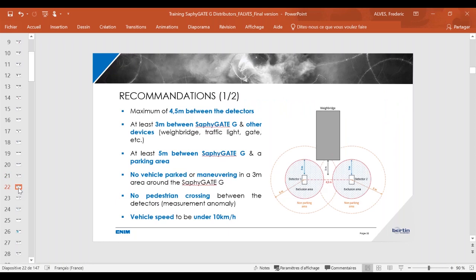Now you have here some recommendations concerning the installation of the system. This is a really important point to keep in mind, because sometimes we have problems after the installation of the system that we could avoid if some points had been checked better before. So all these points are to keep in mind. The first one is the maximum width between the two detectors. The maximum width is 4.5 meters.